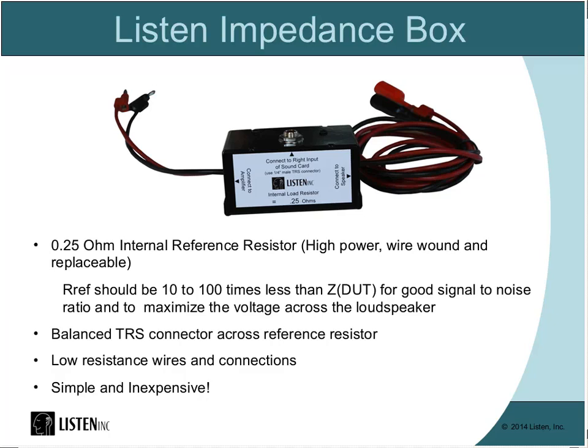It also comes with a balanced TRS connector across the reference resistor, as I mentioned earlier, that will help prevent ground loops and shorts. And it uses low resistance wires and connections. So it's simple and inexpensive, but it's not foolproof.